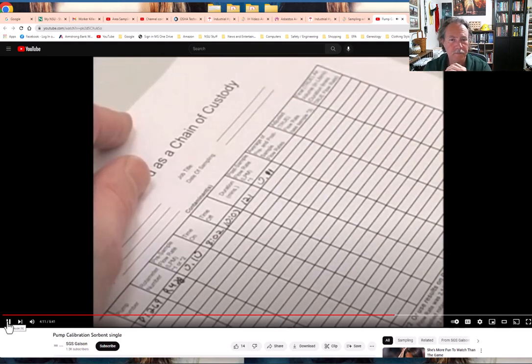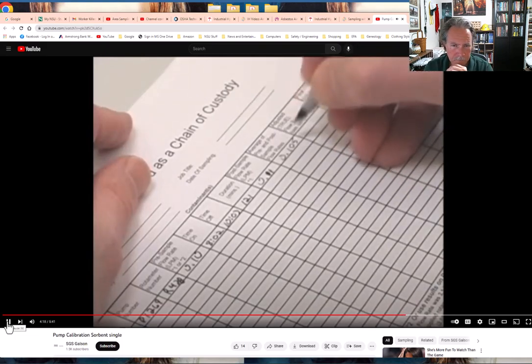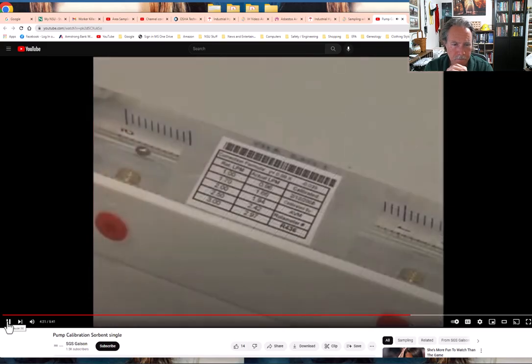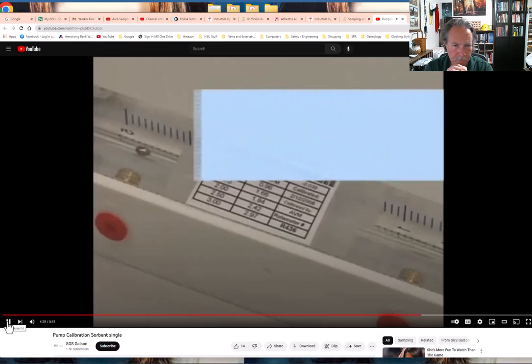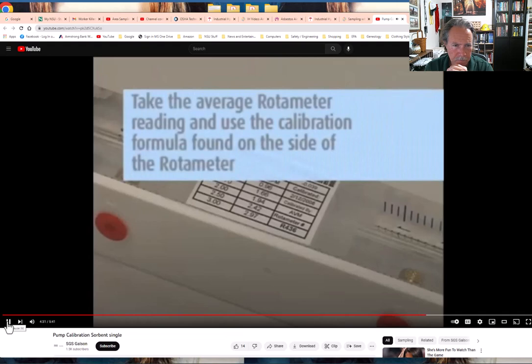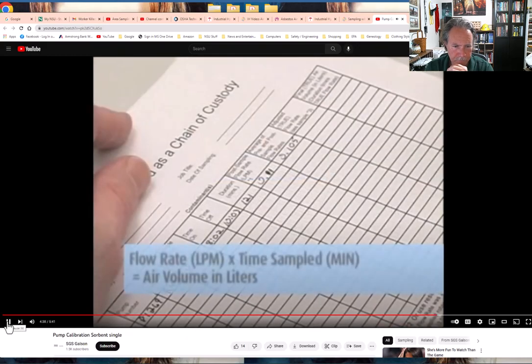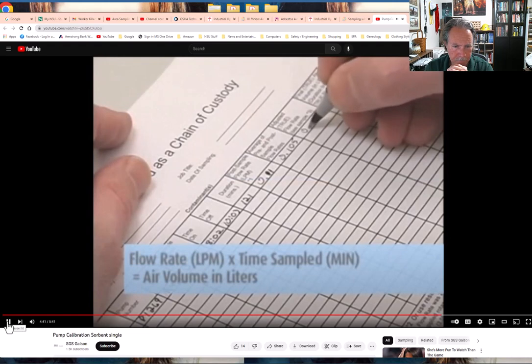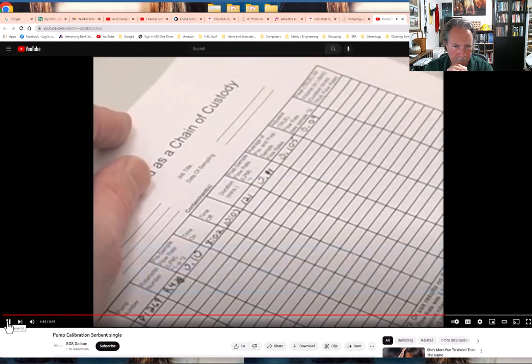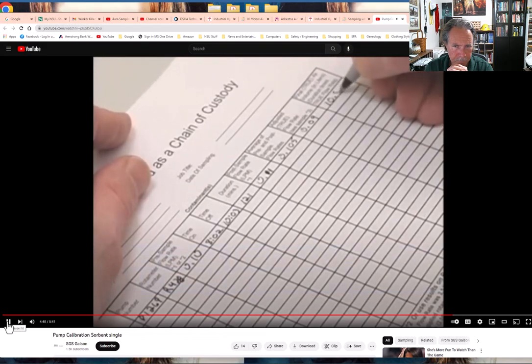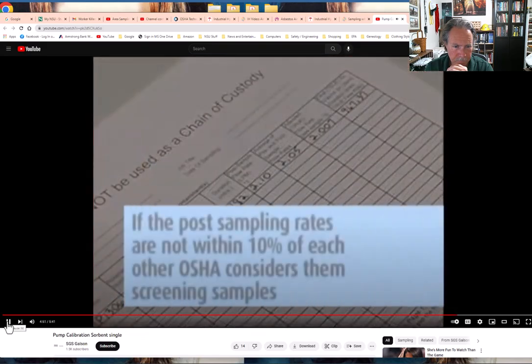The pre and post calibration rates should be within 10% of each other. If they are, average the flow rates to determine the flow rate used to calculate air volume. All rotometers are calibrated against a primary standard quarterly. Take the average rotometer reading, plug it into the calibration formula on the side of the rotometer to determine actual flow rate, then multiply the flow rate in LPM by total time sampled in minutes to get the air volume in liters. If post-sampling rates are not within 10%, OSHA considers the samples screening samples, and if results show high levels, resampling is recommended.